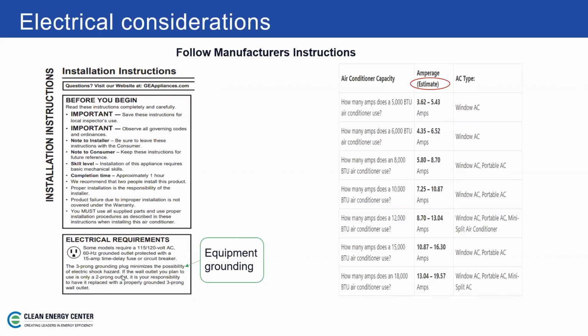The other thing is to think about the grounding requirements, equipment grounding. For the installation instruction for this GE unit, they have a note here: some models may require a 115/120 volt AC grounded outlet protected with a 15 amp time delay fuse or circuit breaker. The 3-prong grounding plug minimizes the possibility of electrical shock. That's what grounds the metal cabinet on the air conditioner, and it's probably going to be required by any local authority having jurisdiction in the municipality you might be working in. So you're going to have to plan to have somebody come in and get you a circuit that's going to be approved.